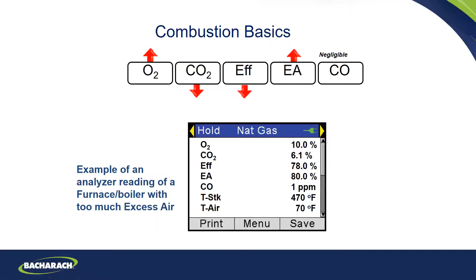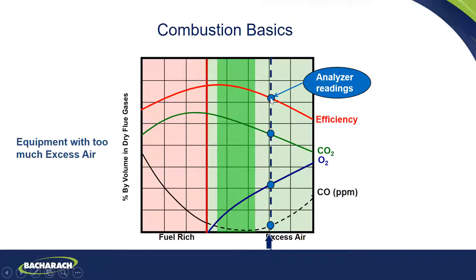Okay. So let's say this was a boiler. Let's work on your gas pressure, make sure that's correct, and then work on an air damper to bring down that oxygen. So here it's showing the oxygen's high. Your CO2 goes down, your efficiency goes down, excess air goes up. So look, your oxygen goes up, your efficiency goes down. So we're going to bring down that oxygen either by correcting your fuel pressure or your air. And where our analyzer was right here, this is where it's reading out with all that excess air. And this line's going to start going this way. Your oxygen's going to start going down. Your efficiency is going to start going up.